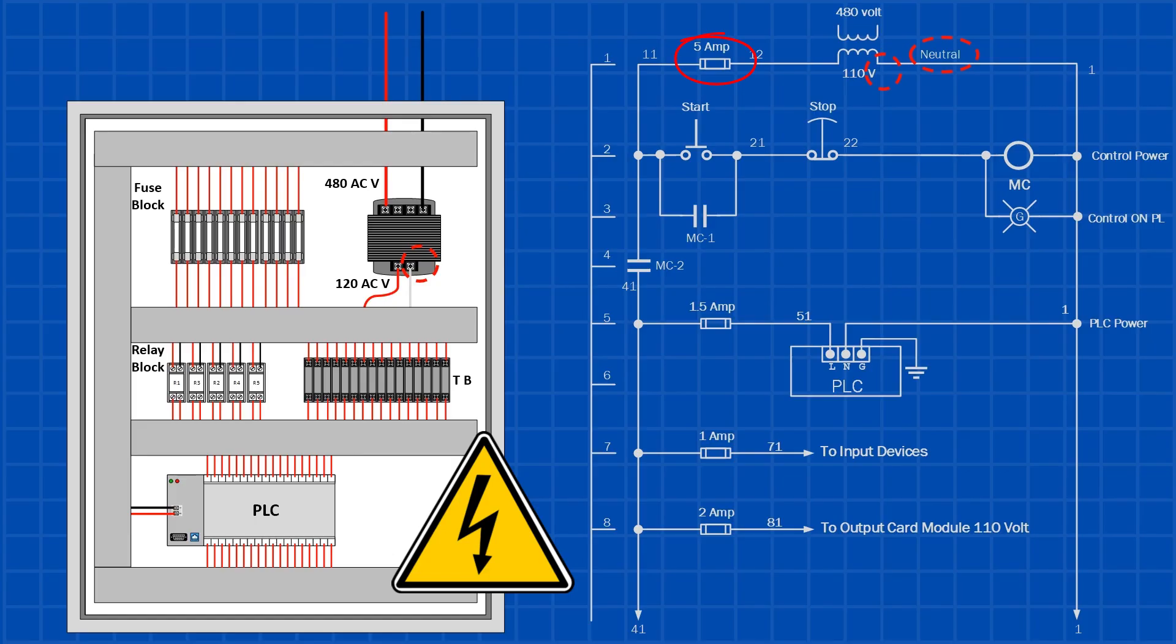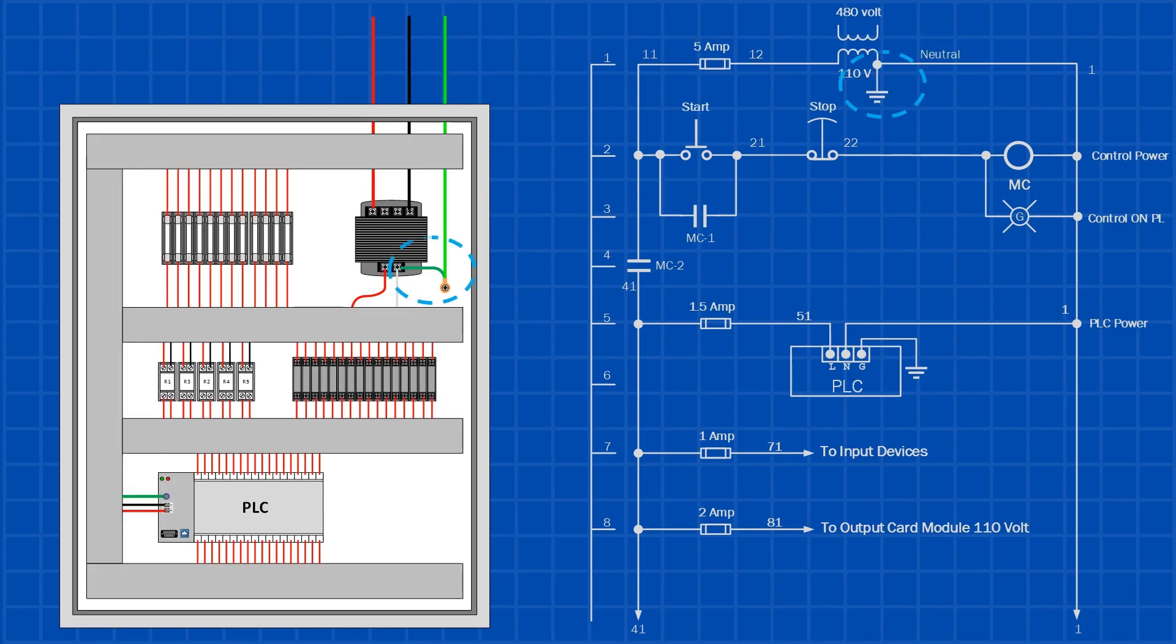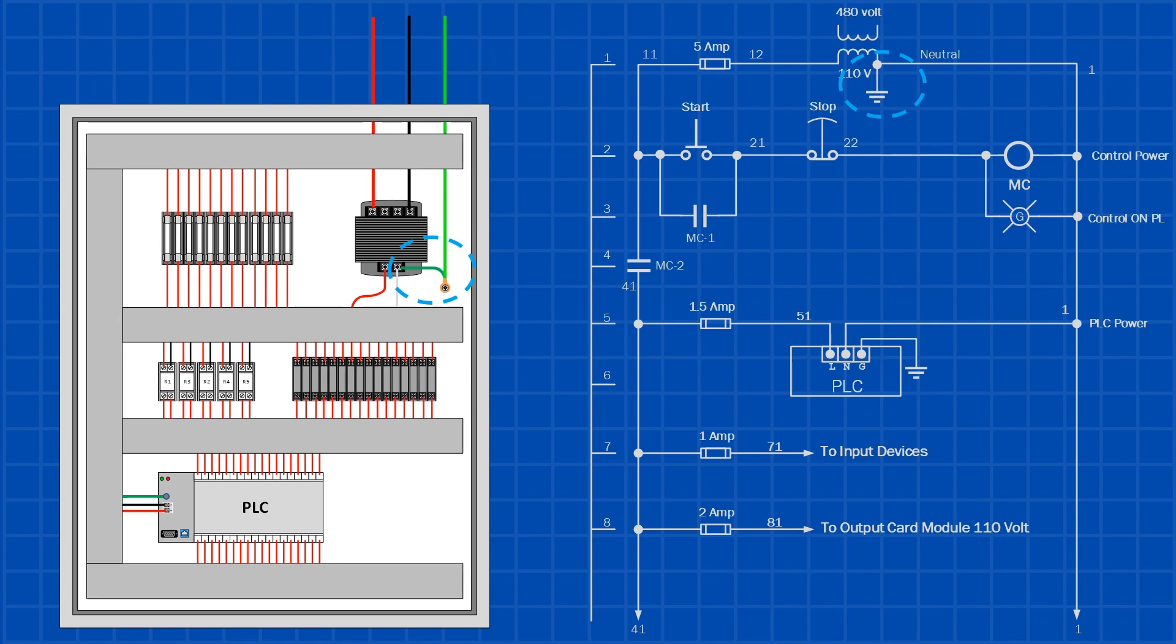That means the entire enclosure becomes dangerously live without anyone realizing it. In a properly designed control panel, the transformer's secondary neutral is bonded both to the panel chassis and to the incoming ground. This ensures that any fault has a clear return path, so the fuse blows immediately, preventing shock hazards and fire risk.